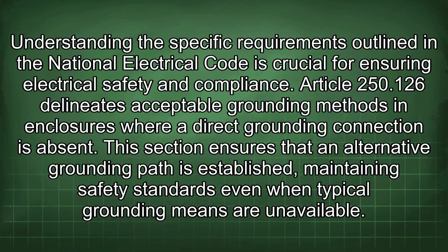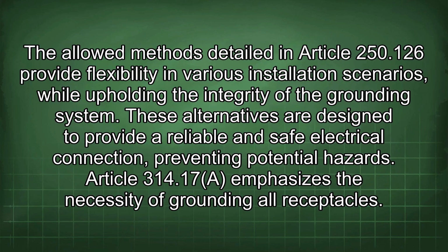Article 250.126 delineates acceptable grounding methods in enclosures where a direct grounding connection is absent. This section ensures that an alternative grounding path is established, maintaining safety standards even when typical grounding means are unavailable. The allowed methods detailed in Article 250.126 provide flexibility in various installation scenarios while upholding the integrity of the grounding system. These alternatives are designed to provide a reliable and safe electrical connection, preventing potential hazards.